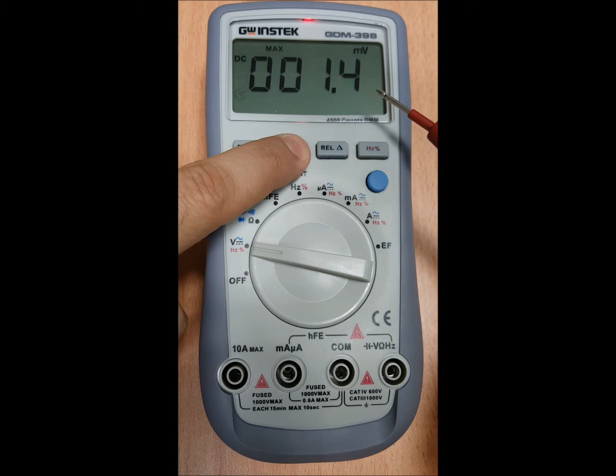For the next one, which is REL, pressing one time will get the multimeter into the REL mode, which will basically subtract the actual value from the stored value, which can sometimes be confusing. So always make sure you don't have this logo on. Pressing REL for a few seconds will switch on the data connectivity mode, which is not supported by this model, GDM398. So this will be there based on the internal setup of the multimeter, but there is no way to get the data out. Some other models you can connect via USB or RS232. So you will need to press again for 3 seconds to get the screen back to its normal value.